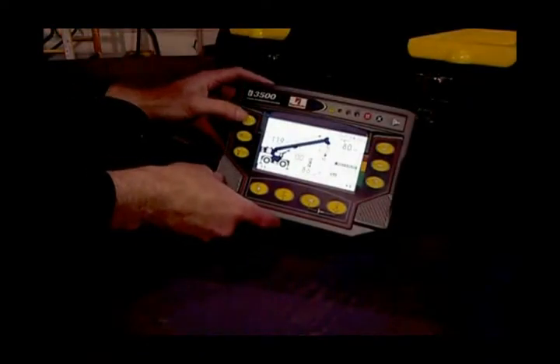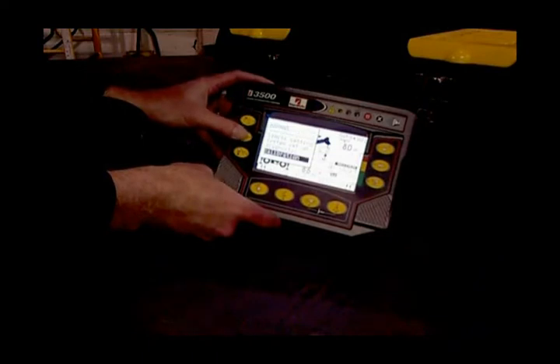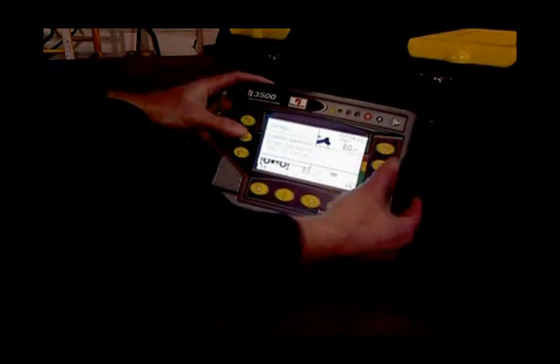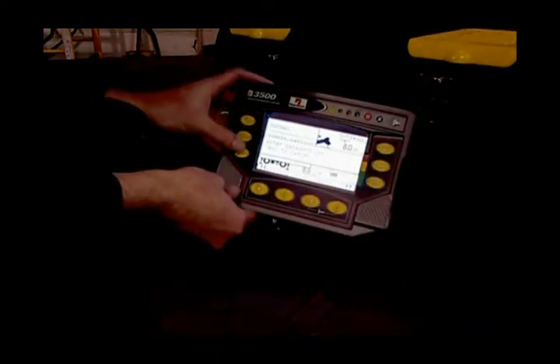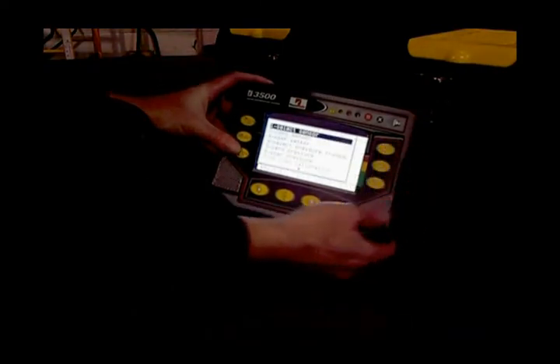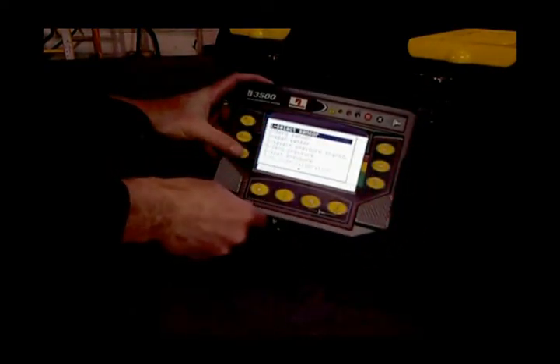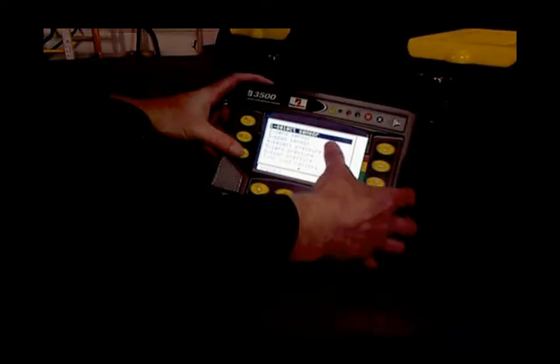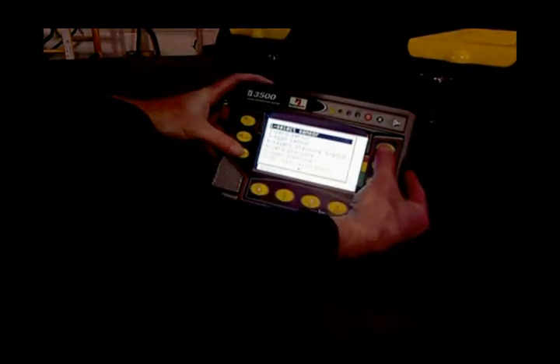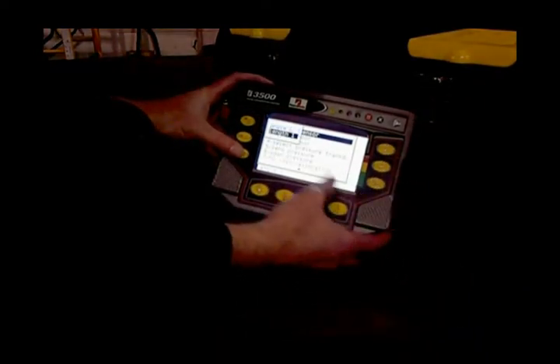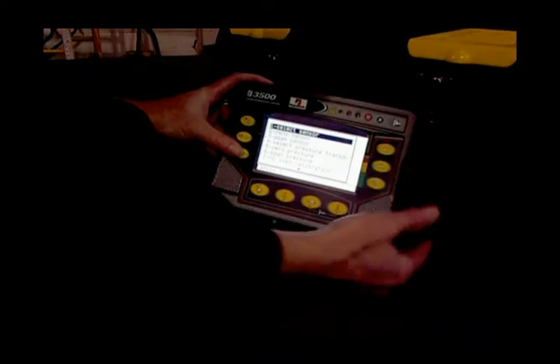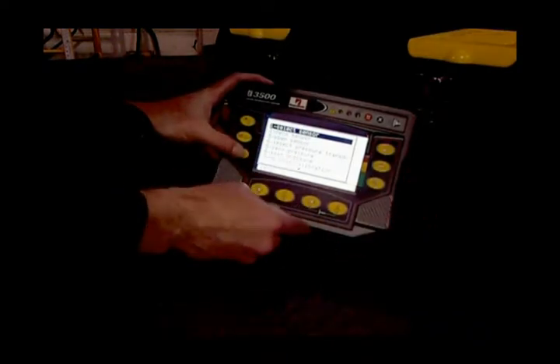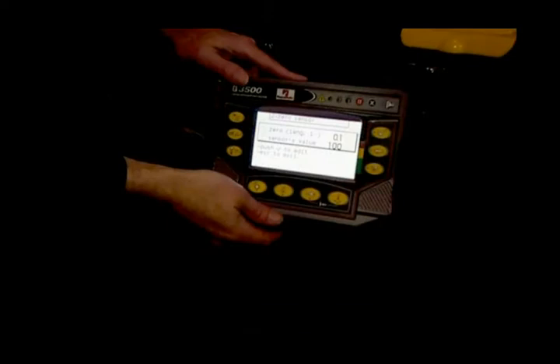What we want to do is go over to calibration mode now and enter the password 1, 2, 3, 4. And we're going to make sure that we have the correct sensor selected. So it's already sitting on select sensor. We're going to hit the check mark, drop it down to length 1, hit the check mark again, and now we're going to drop it down to zero the sensor.